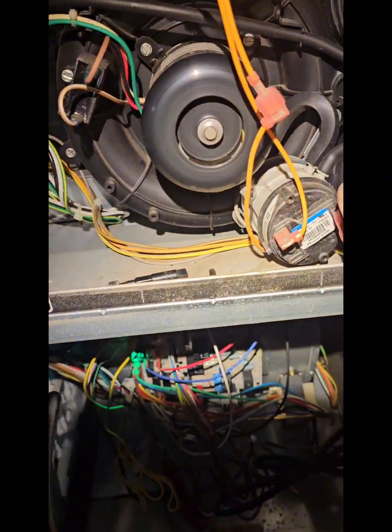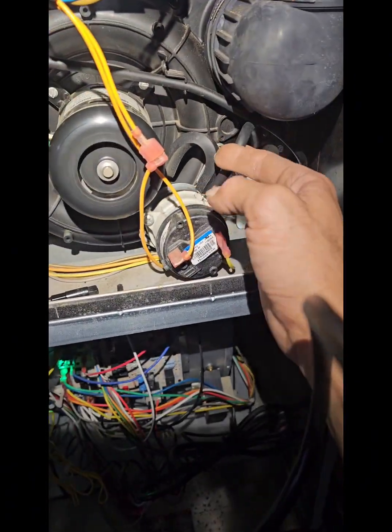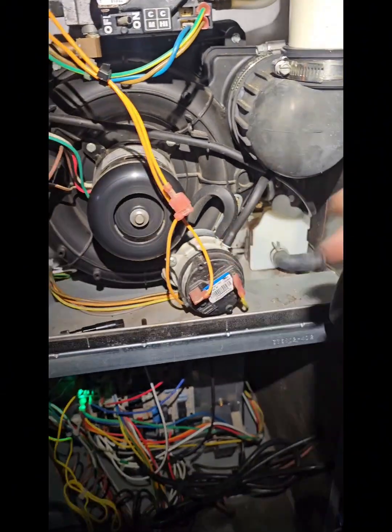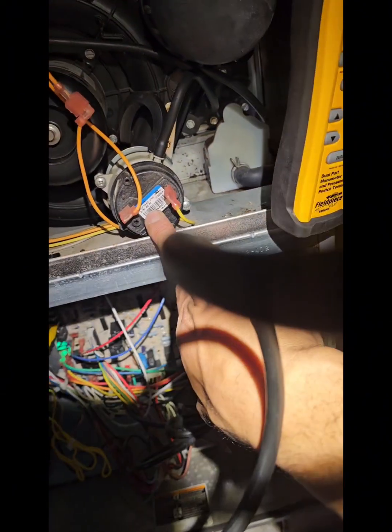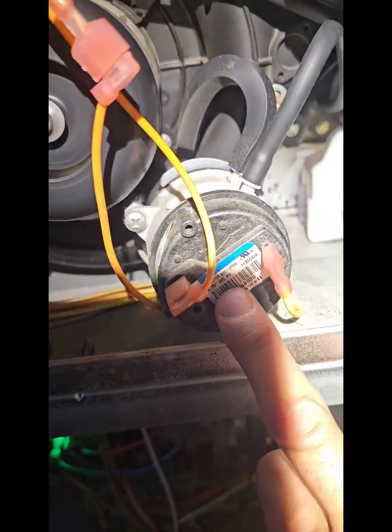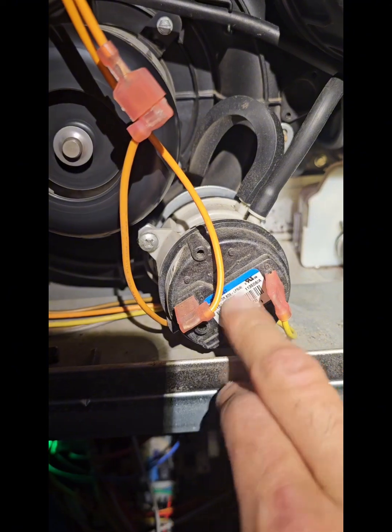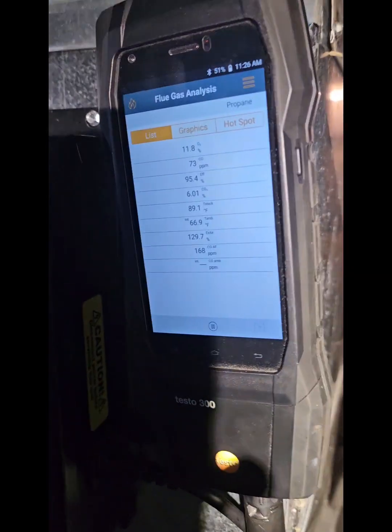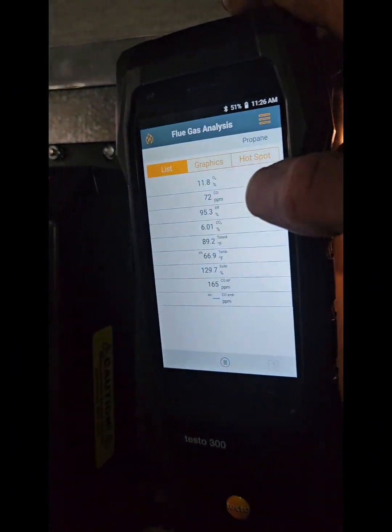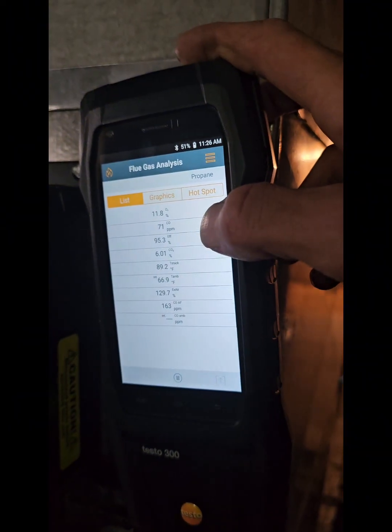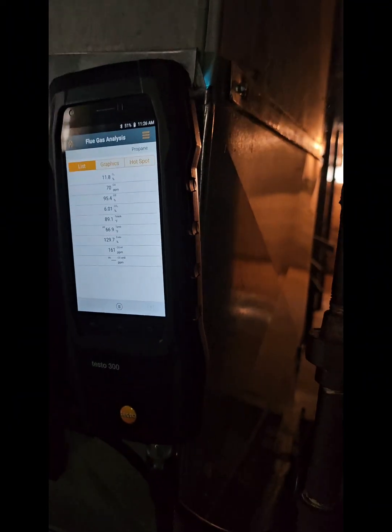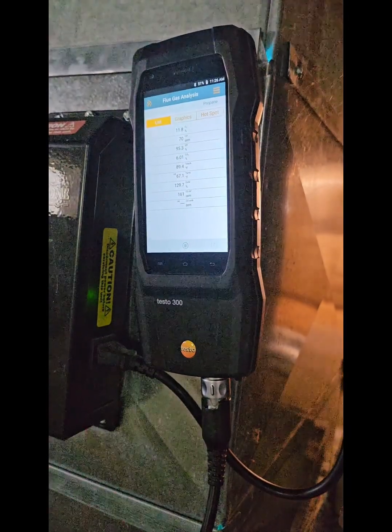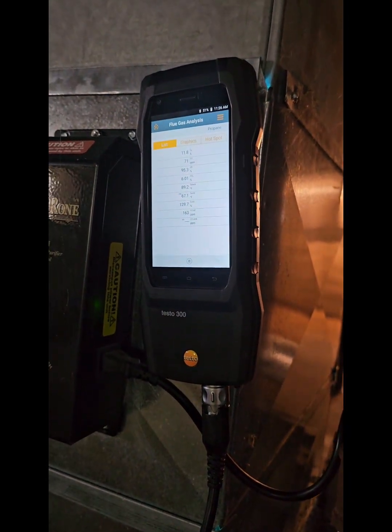And the way that I'm going to test the inducer is to pull this hose off and put it on my manometer. After I'm done measuring all this stuff, we'll pull this hose off and put it on the manometer and make sure that it's pulling significantly above the vacuum that the pressure switch is rated for. And so we see the combustion analysis, the CO right here has stayed at 70, which is still relatively high. Okay, I think for me, 60 parts per million, and I'm going to start asking questions or trying to figure out what's going on with that.